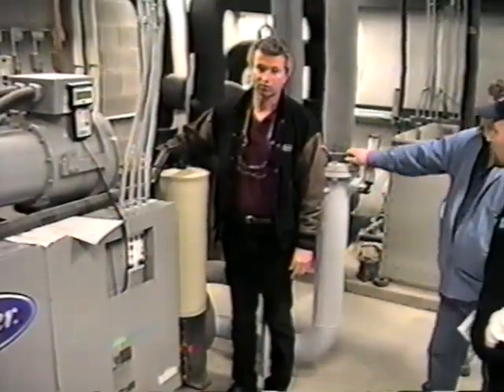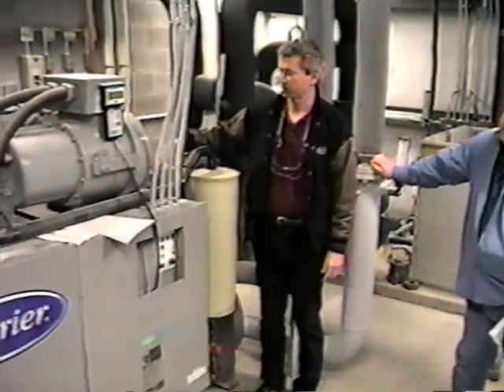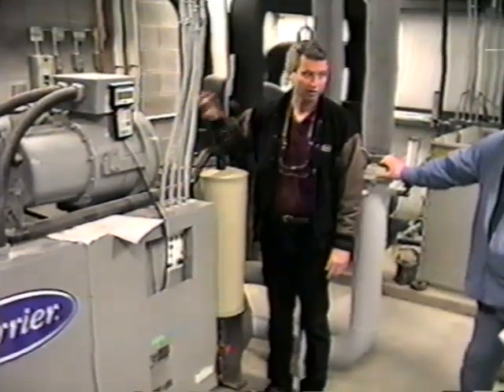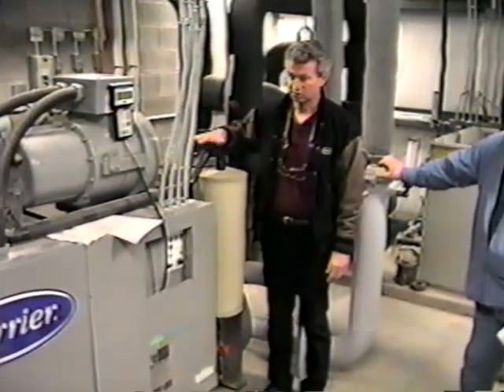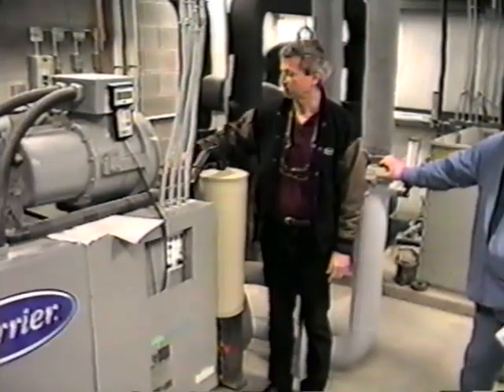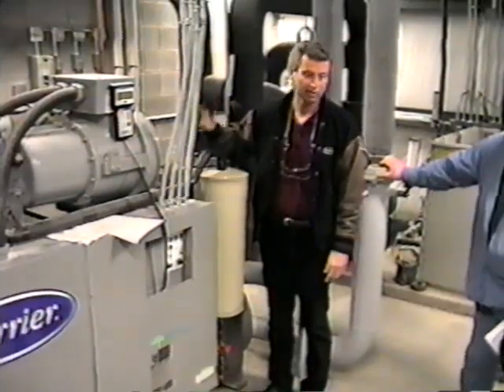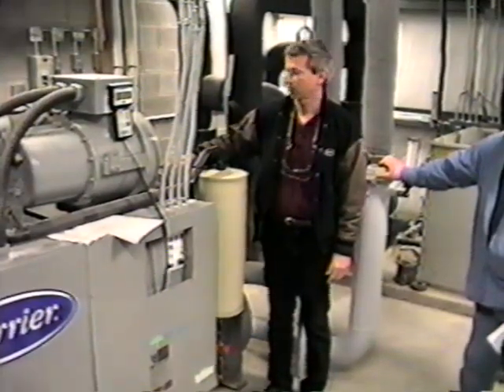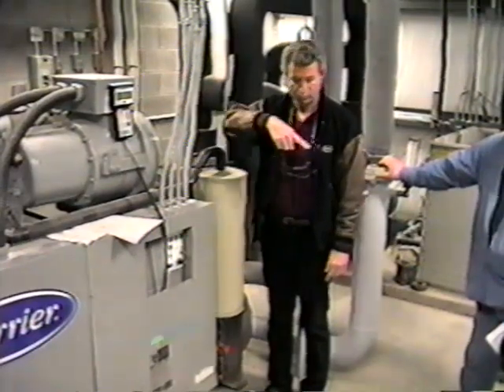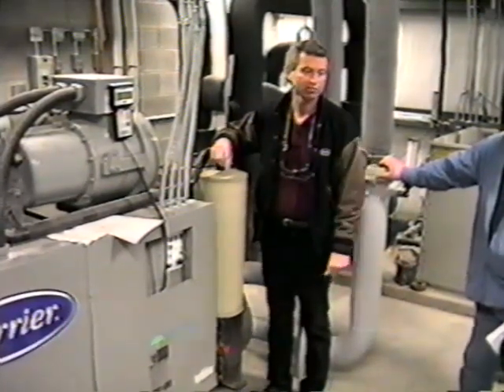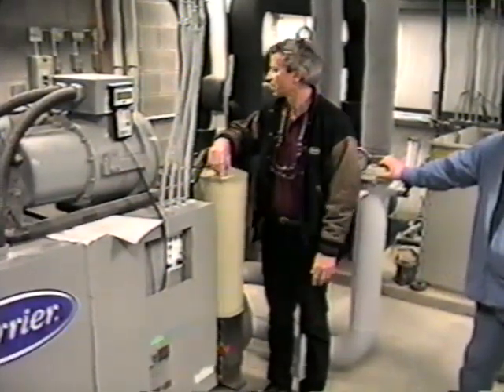When the motor gets up to 160 degrees and above, this cycles and injects a shot of liquid. We're constantly pulling gas through there, but it essentially needs a little additional liquid to keep the motor running at the temperatures we want. And that temperature you can read out in your logs, so that was one of the temperatures I recommended you take.